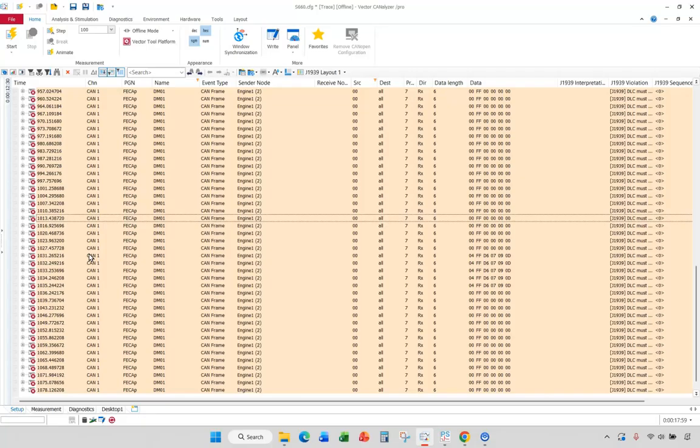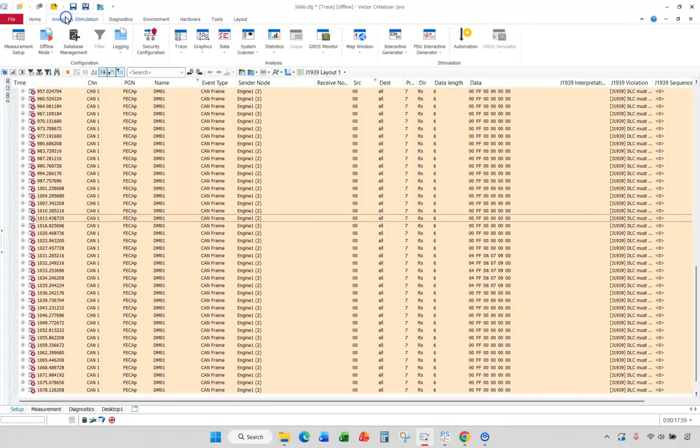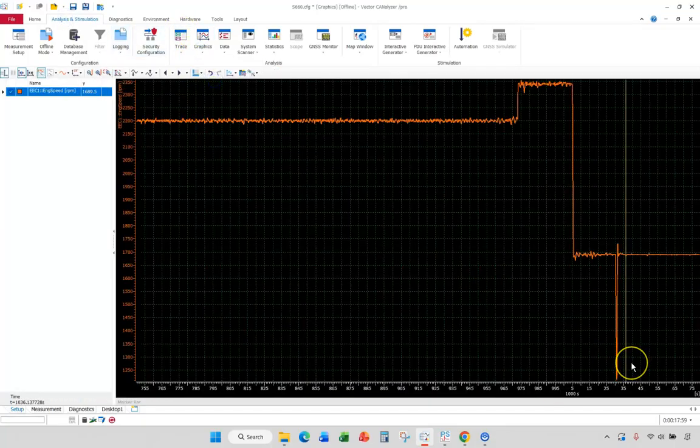John Deere technicians are probably very familiar with this diagnostic trouble code because it's probably one of the most hair-trigger diagnostics that there are. That's very important, this communication from this vehicle controller. What is the engine requested speed? Obviously, if that controller that's requesting it from the engine stops communicating for any reason, the engine controller really doesn't have much choice as to what to do with engine speed other than something like this.